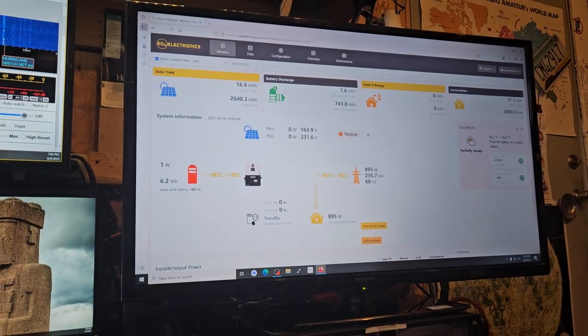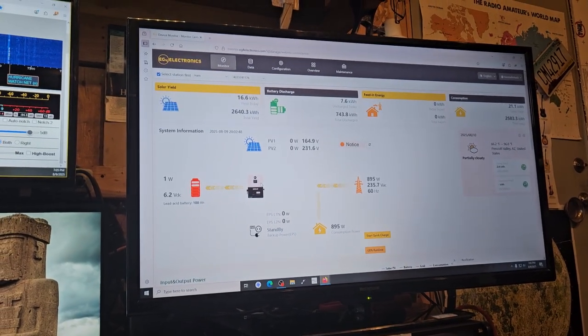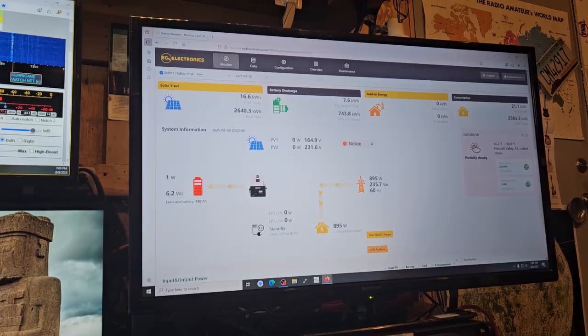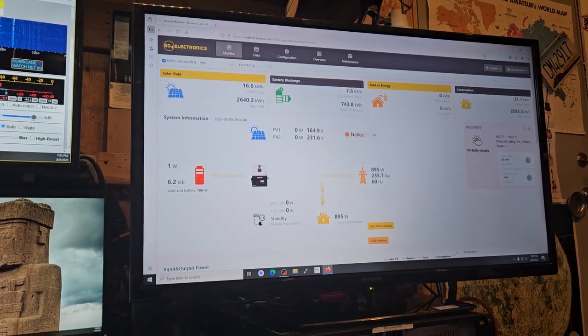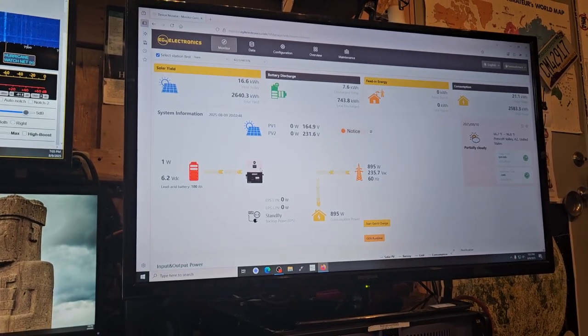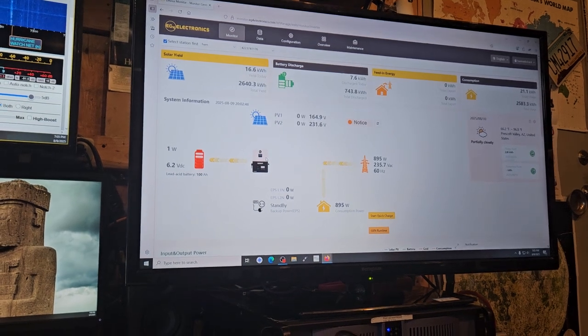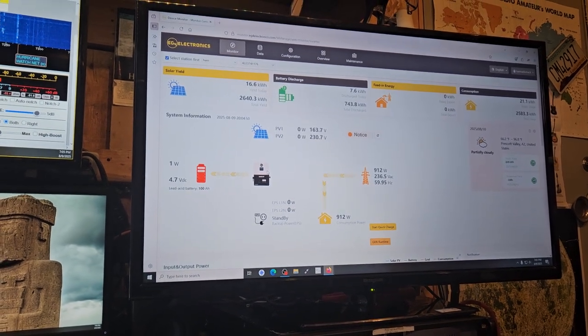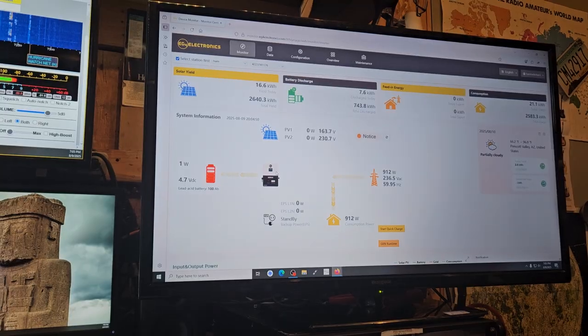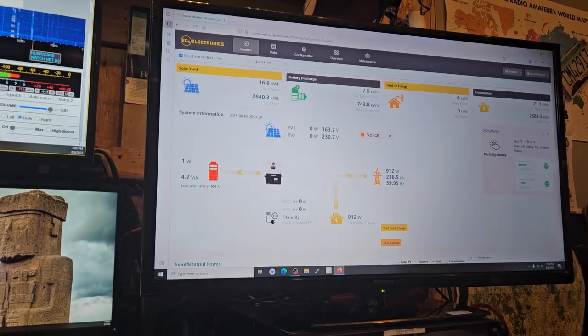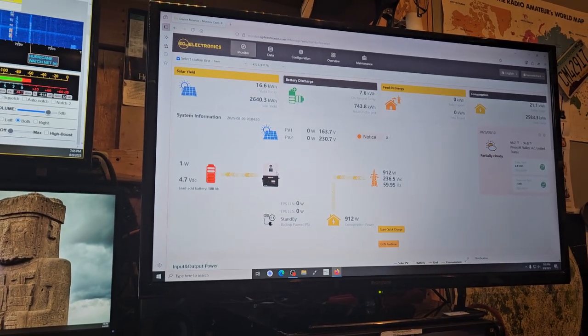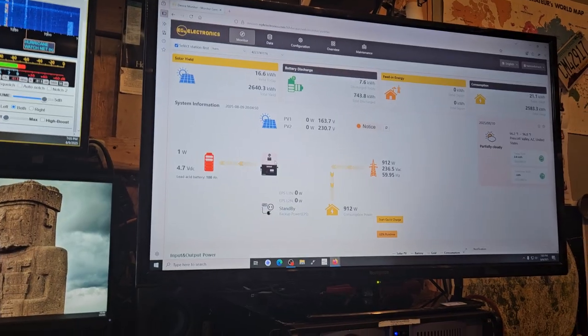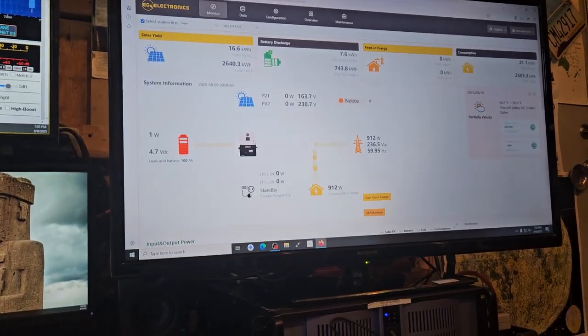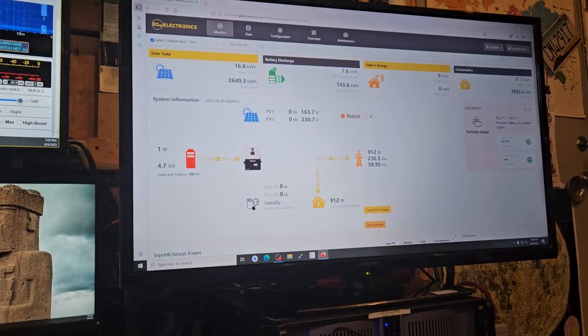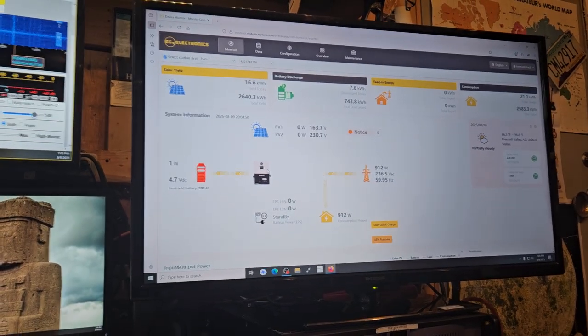That's what I read about other people doing—they'd tell it to charge from this time to this time and shut off at this time. But if you don't have instructions for this thing to shut off from the grid, and you're running all your critical loads on it, expecting it to get to 54 point whatever volts, it's never going to make it. You're never going to be able to use your solar. You're going to have to go in and turn this stupid thing on and off manually. It's really stupid.